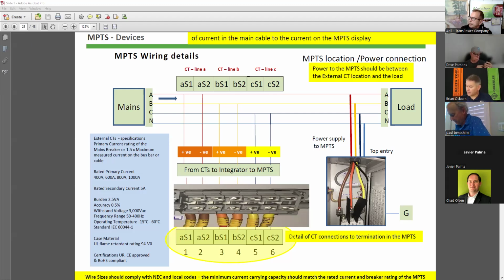That's good information, that it doesn't have to be directly placed next to the service equipment. If space doesn't allow, you could find an adjacent space and then run a raceway to the point of common coupling.